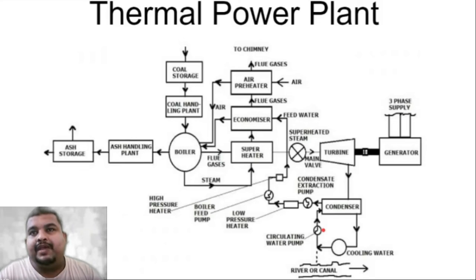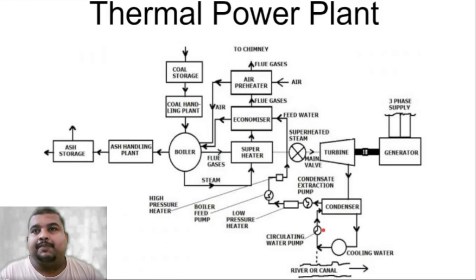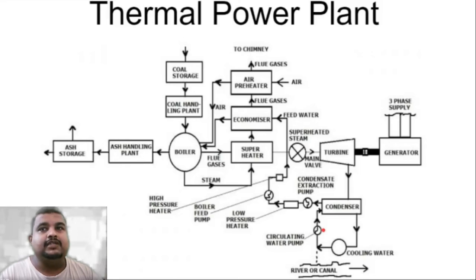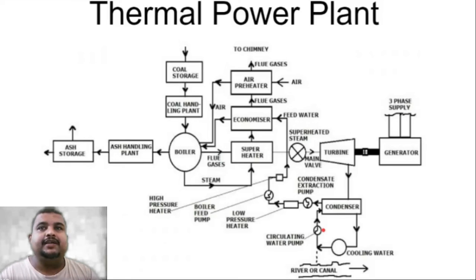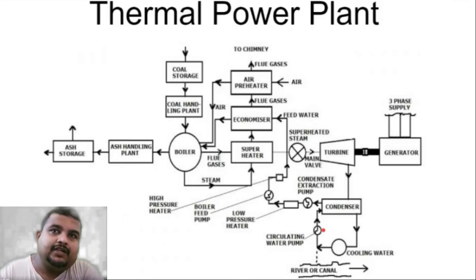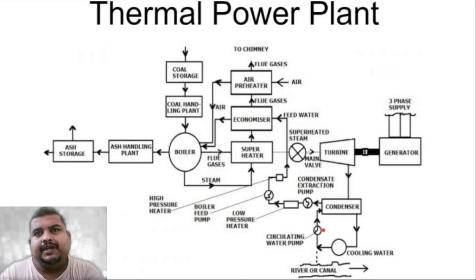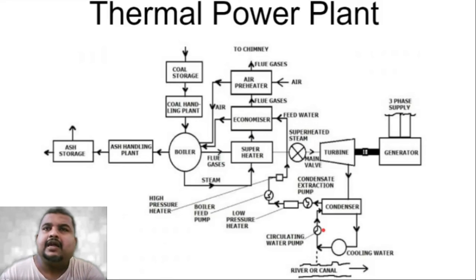The superheated steam is delivered to the turbine via the main steam line as high pressure steam. To recap the complete feed water and steam cycle: turbine → low pressure steam → condenser → cooling water → CEP → low pressure heater → BFP → economizer → boiler → steam → superheater → back to turbine. Note that in the diagram the superheater is shown outside the boiler, but in real life the superheater mechanism is inside the boiler.